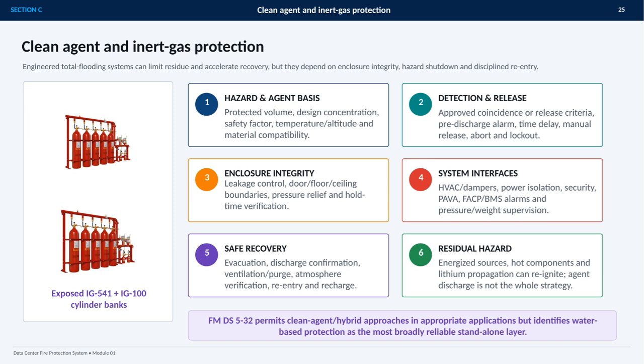The system also has to interface with HVAC and dampers, power isolation, security, voice alarms, the fire alarm control panel, building management systems, and cylinder pressure or weight supervision. Safe recovery includes evacuation, discharge confirmation, ventilation, atmosphere verification, controlled reentry, and recharge. Finally, energized equipment, hot components, and lithium battery propagation may reignite, so residual hazards require additional controls. FM DS 5-32 allows clean agent or hybrid approaches where appropriate, while identifying water-based protection as the broadest reliable standalone layer.